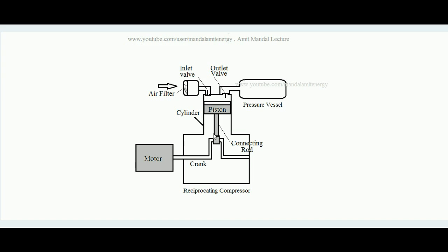This is the schematic diagram of a reciprocating compressor. It consists of a cylinder and a piston that reciprocates inside the cylinder. It has two valves: the inlet valve and the outlet valve — these are non-return valves that can open on one side only. There is a crankcase and a crank driven by a motor, so rotary power is provided by the motor to the crank, and this rotary motion is converted into the reciprocating motion of the piston.